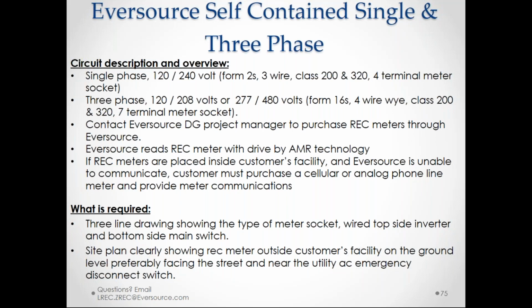Again, we prefer the high-powered ERT meters that can simply operate with a drive-by meter read technology where we pick up the radio frequency signal. If they're placed inside, that's where we have a difficulty or potential difficulty for picking up those high-powered meter readings. So our preference is always outside. If there are extenuating circumstances where it must, for some reason, be installed in the interior, we'll review that on a case-by-case basis and determine if we can, or must, go to a cellular or a phone line type of meter. So what do you have to show on your line diagram?